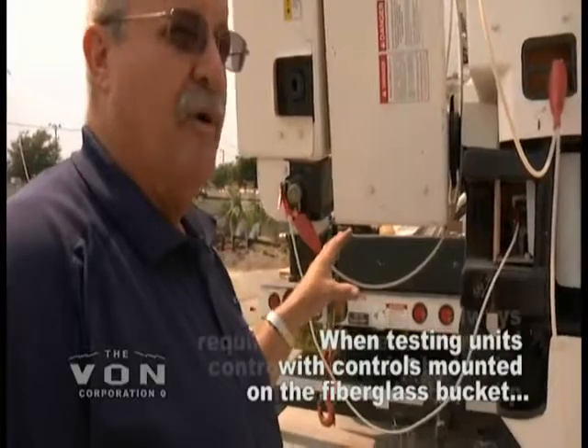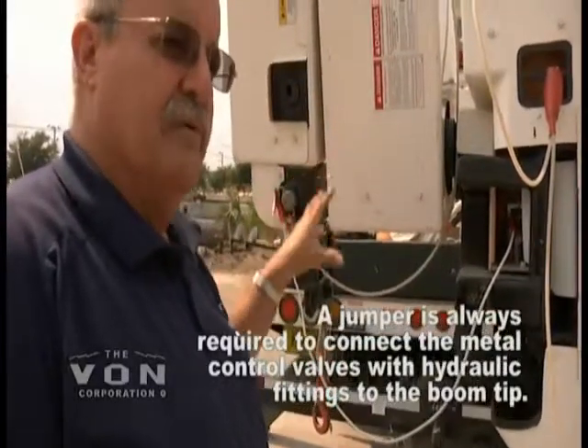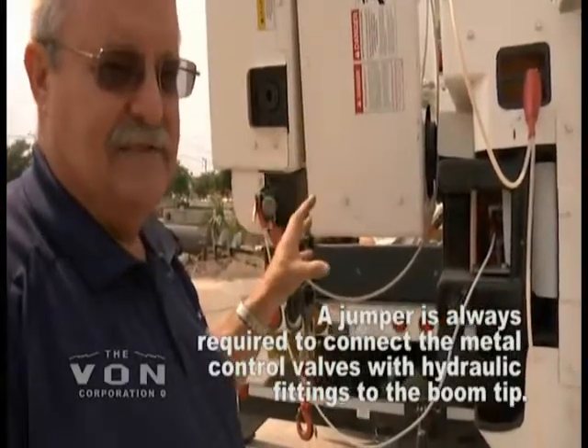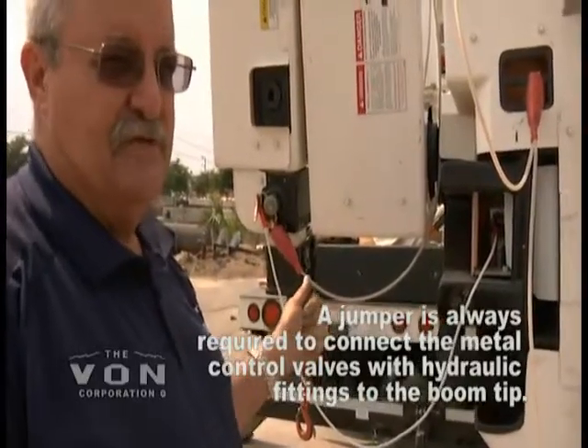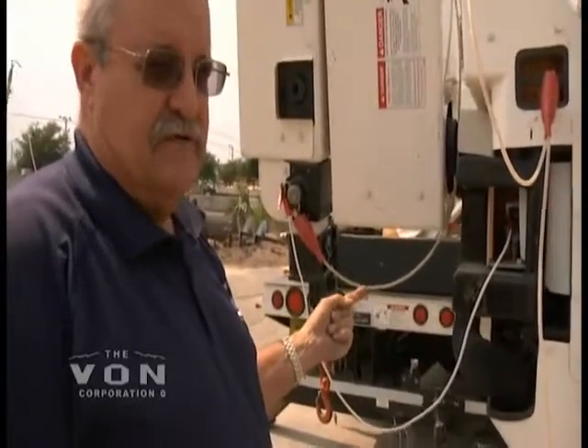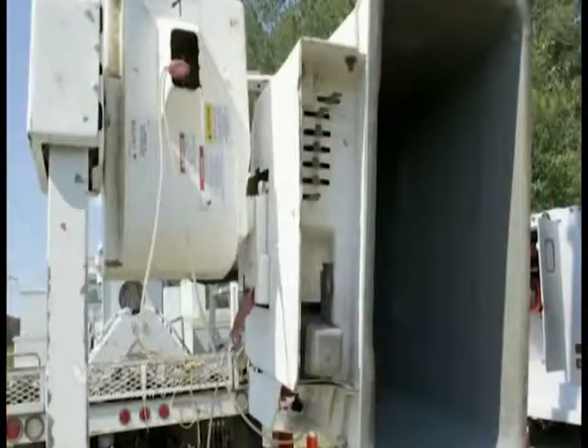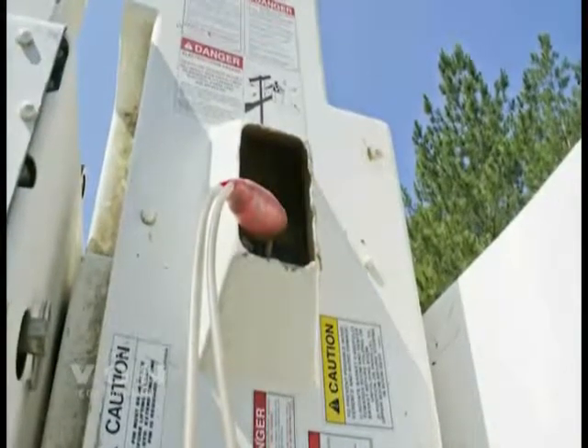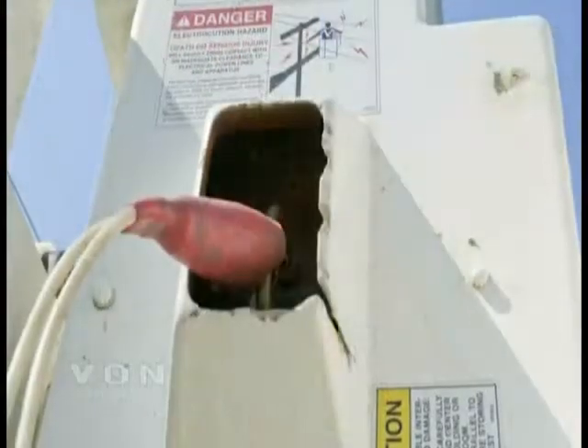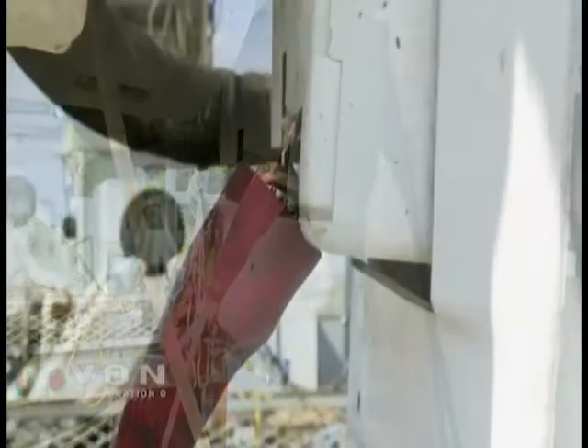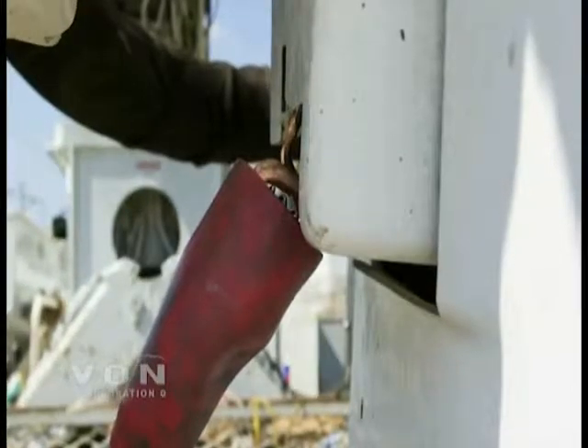The boom is energized inside and outside. The hydraulic lines are energized. The hydraulic oil is energized, and it's all tested in one test. Every manufacturer designs their trucks differently. When you are out in the field testing these bucket trucks and digger derrick trucks, you will find several different types of mounting of the buckets and the boom tips. It is necessary for you to attach to all metal parts with your high voltage leads.